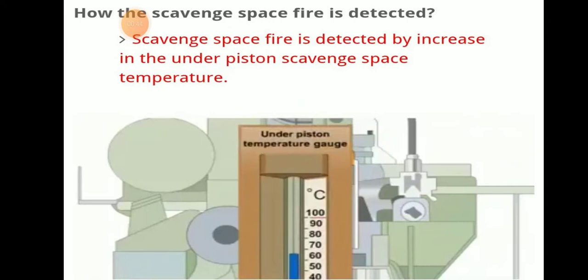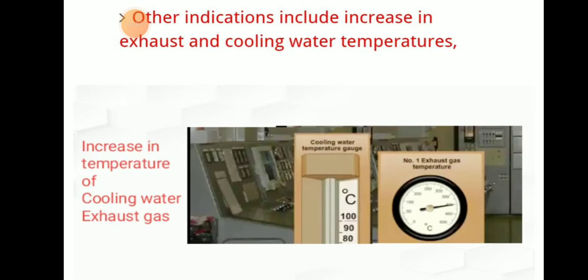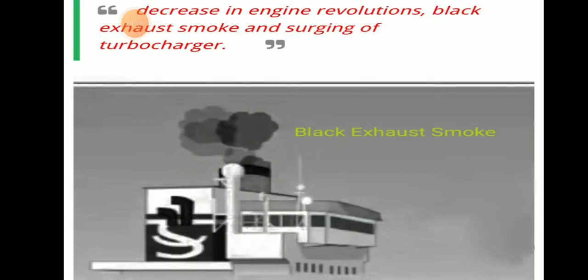Scavenge space fire can be detected when the under-piston scavenge space temperature increases — that is the first indication of scavenge space fire. Other indications include increasing exhaust temperature and cooling water temperature. There will also be a decrease in engine revolution, meaning RPM is reduced.